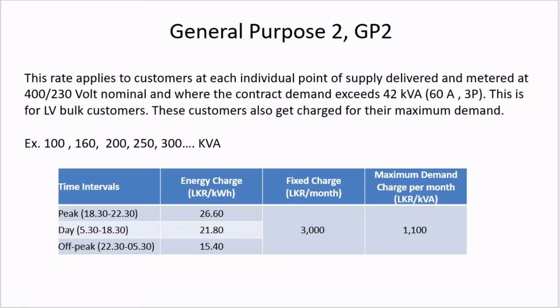This is GP2, where customers are charged for time of usage, and at the meter there's also a demand meter. If you have a GP2 supply from the CEB, they will fix the maximum demand meter next to your unit meter and charge for the maximum demand too. Maximum demand is measured in kVA, which is apparent power. This is mainly done to encourage power factor correction, so if you have very high reactive power, the apparent power goes up and you get a very high charge.